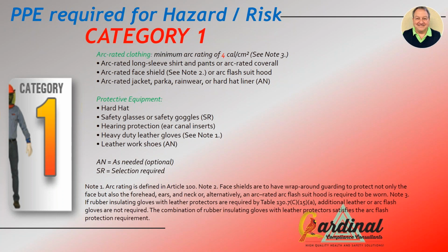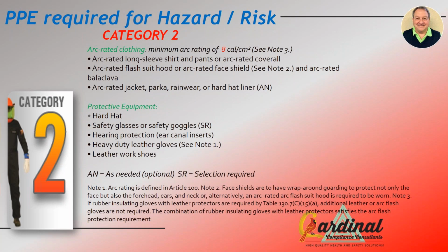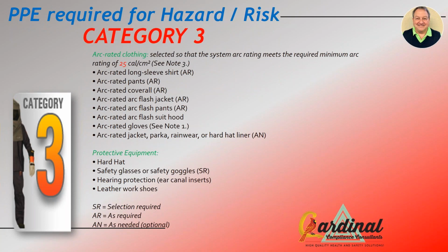Category 2 rises up to 8 calories per square centimeter. The clothing gets heavier, and now we also need protection for our neck area. Why? Remember we talked about the sound wave and the pressure wave that comes out from an arc flash? It's now to the point where it could collapse your windpipe and cause real trouble in breathing. So we need to be protective of those hazards that we face as electrical workers. As you go to Category 3, traditionally these might be a jumpsuit or a pullover going over the top of electrical gear to gain this higher level of 25 calories per square centimeter protection.